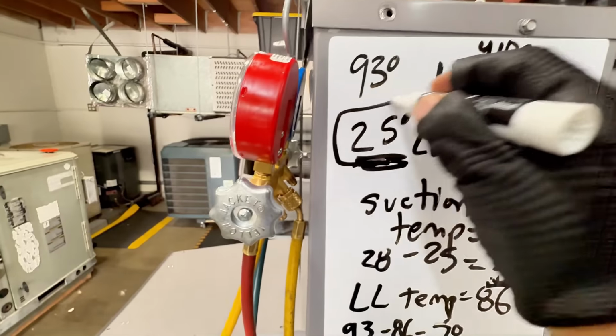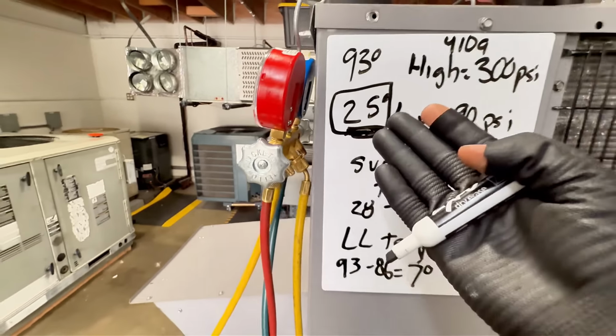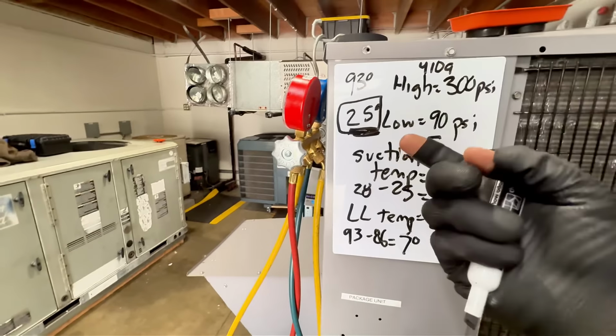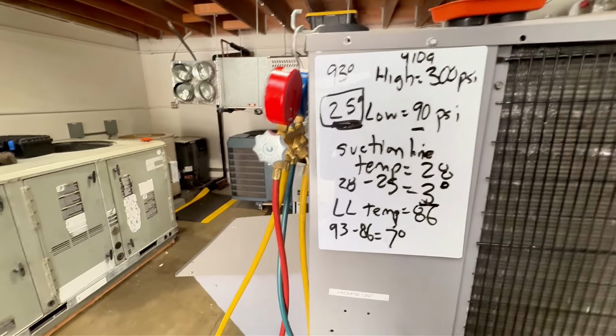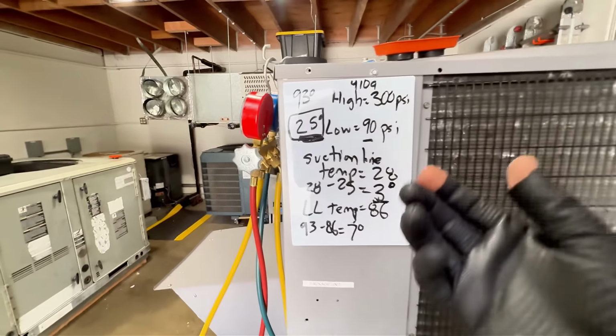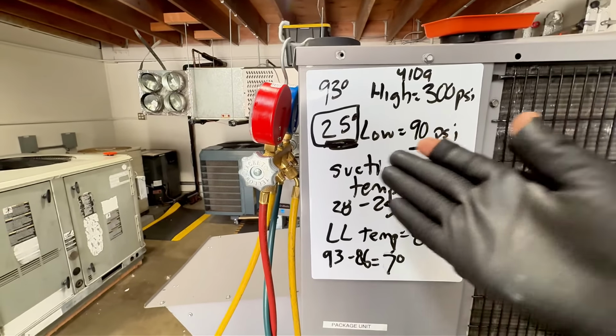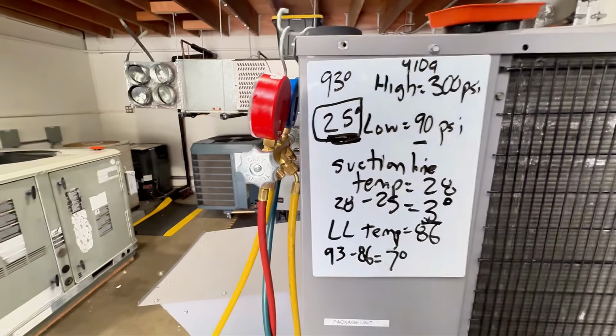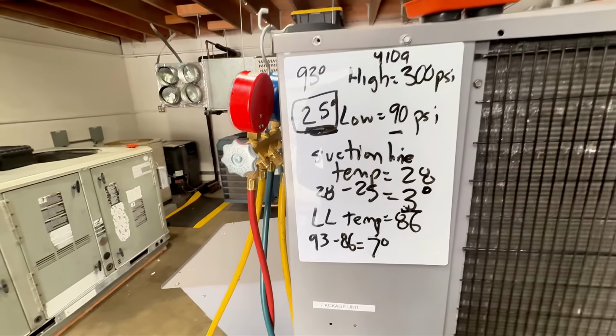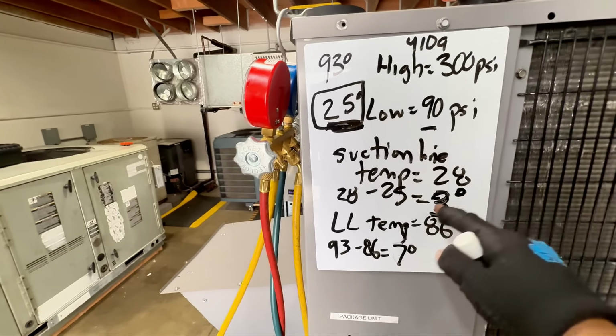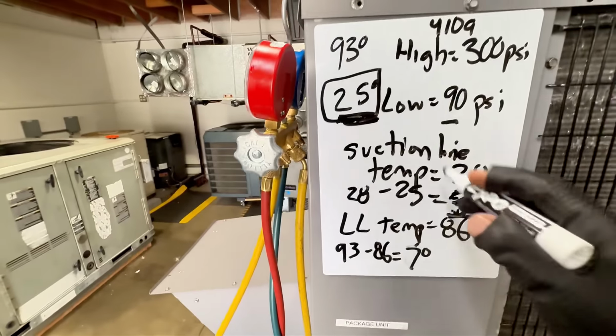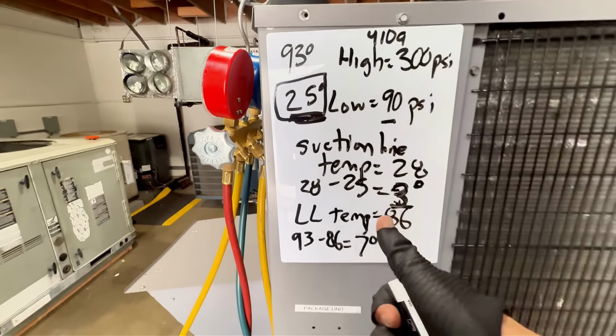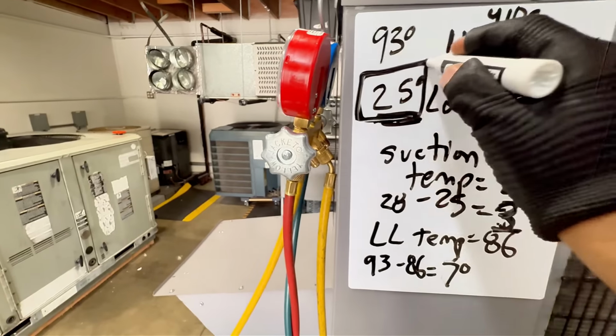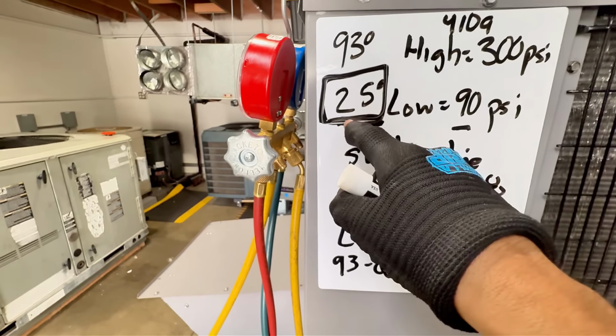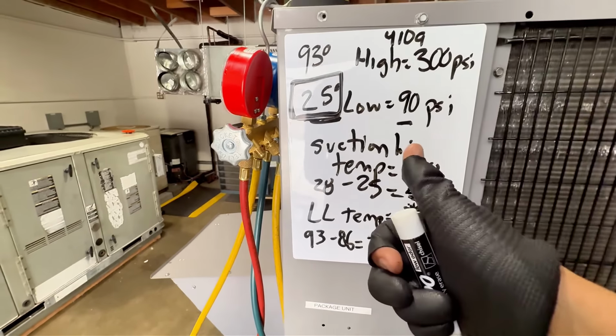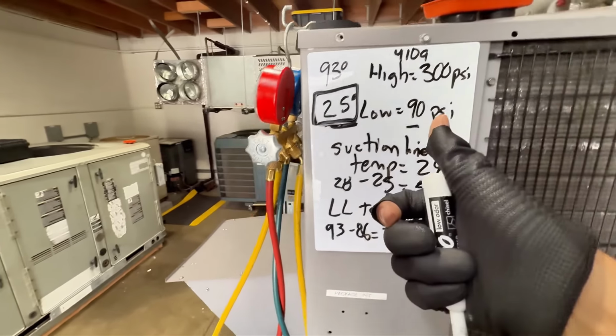But I'm scared about this number here. It's below 32. So for me, right away, I'm saying the fan speed is too low. What else? It's overcharged, right? And it could trick you into thinking it's overcharged. Don't let it trick you, because you can be like, oh, it's low, there's too much liquid refrigerant. But the key is, if it was overcharged, your suction pressure would be really high, but it's low. So we got a low evaporator temperature, low superheat. Going back to the airflow issues: low airflow, like fan speed.